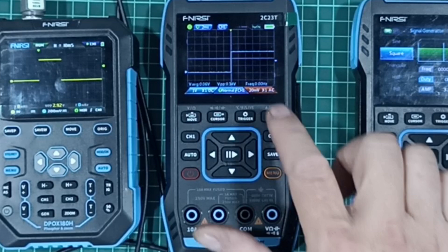If you've got a repetitive signal, they're awesome. For a single pulse, they just don't trigger constantly or reliably, which makes it bad for working on X-ray units where you want to have a single wave that you need to capture and look at. I've been babbling for a good couple of seconds now, and this has never updated to the latest one. It had finally updated once, and that's a problem with this. It will update once in a gazillion samples, which doesn't help you.